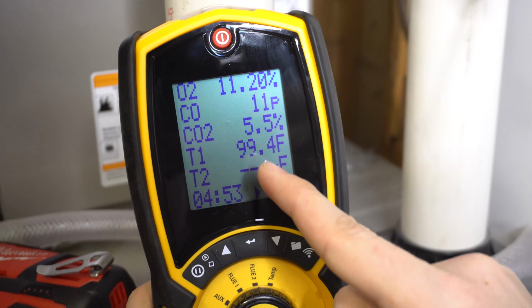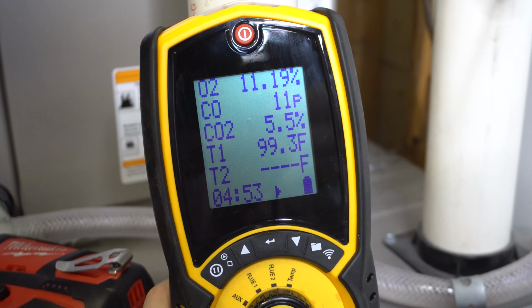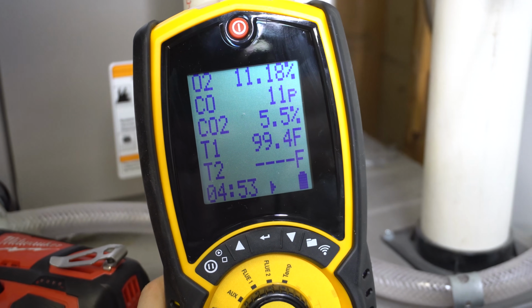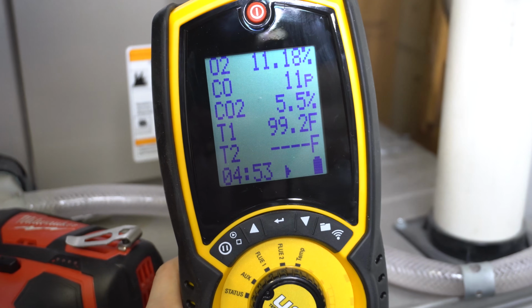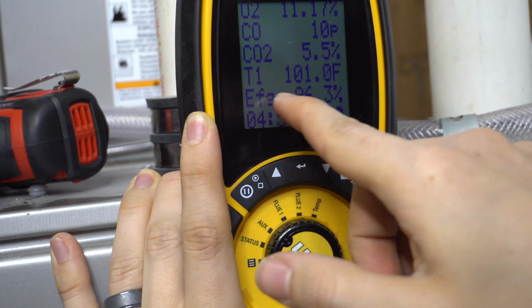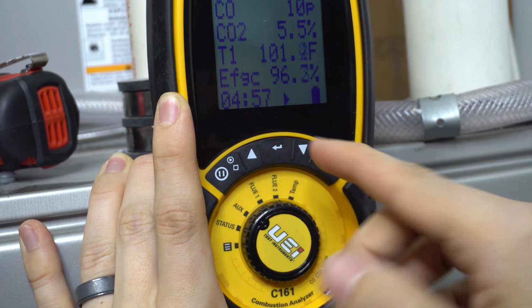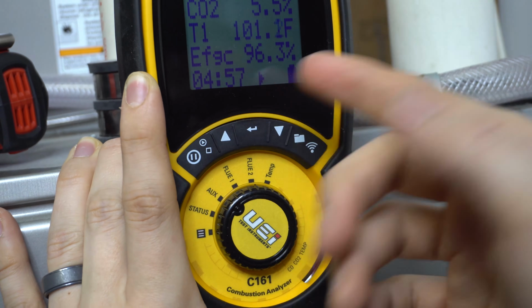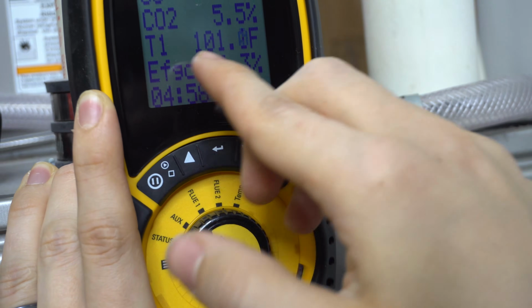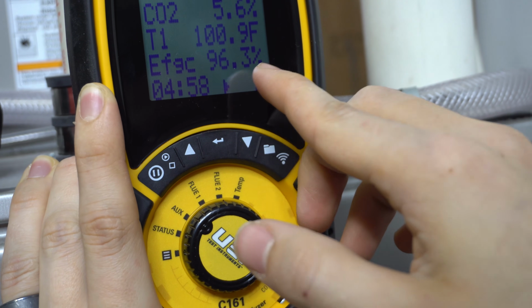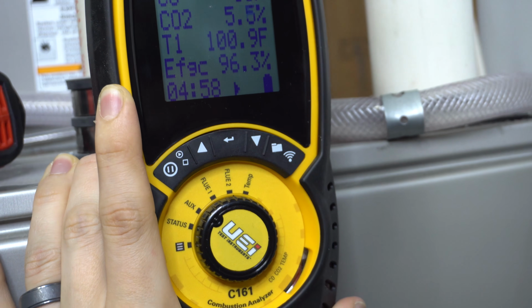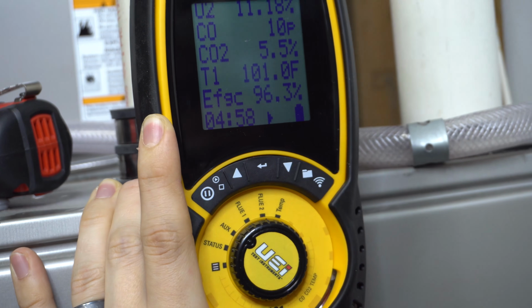And this is low stage. Once this kicks into high stage, the temperature should go up, and I'll wait for it to kick into high stage so we can see that. Oh, and I almost forgot, instead of T2, because I don't ever use it, I usually have the efficiency instead, the gross calculation. So our gross calculation for efficiency is 96.3%. For a high efficiency furnace, that's actually very good, 96% efficient.